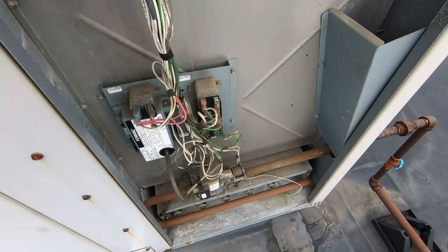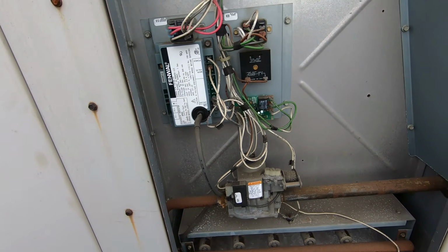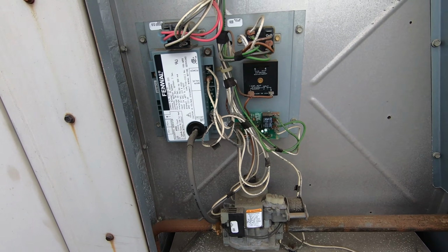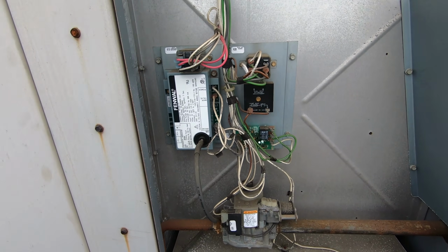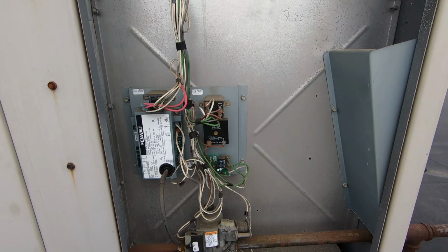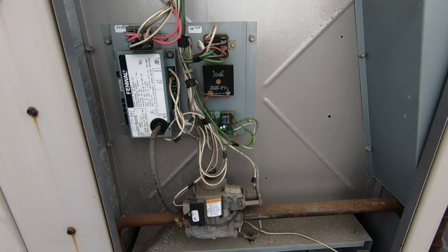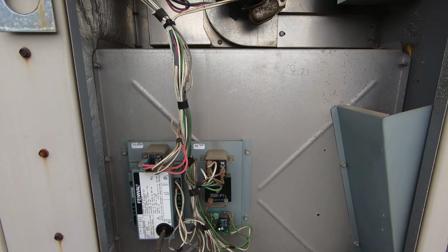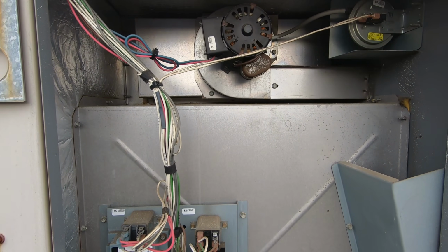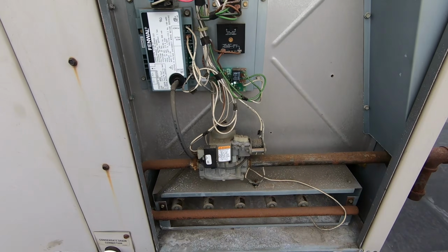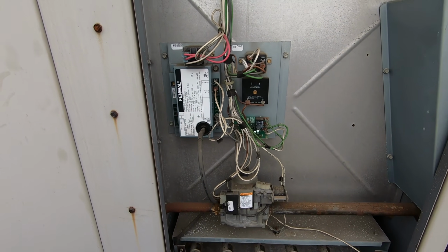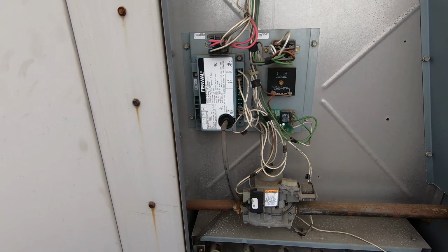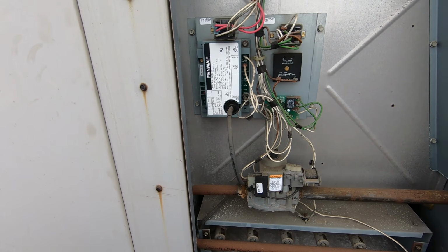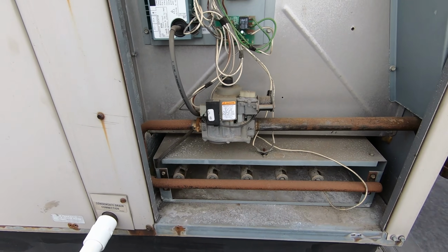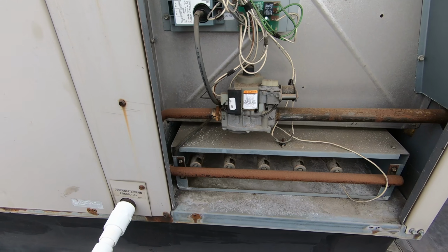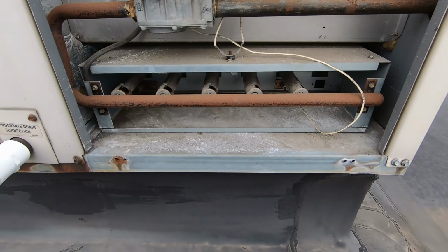All right, I disconnected 24 volts and turned the power on. I've got 28 volts and it did not trip. I've got a call for heat. Well, let's see what happens. Combustion blower doesn't sound too good. I'm assuming it's one of these relays or this ignition control module, possibly even the gas valve causing that. And we lit up.